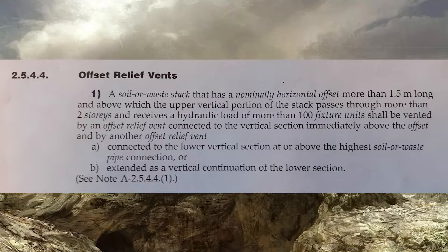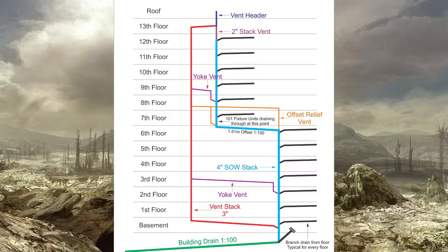Clause 2544: A soil-or-waste stack that has a nominally horizontal offset more than 1.5 meters long, and above which the upper vertical portion of the stack passes through more than two stories, and receives a hydraulic load of more than 100 fixture units, shall be vented by an offset relief vent connected to the vertical section immediately above the offset, and by another offset relief vent: A) connected to the lower vertical section at or above the highest soil or waste pipe connection, or B) extended as a vertical continuation of the lower section. There's a lot to unpack there, so let's break this down.